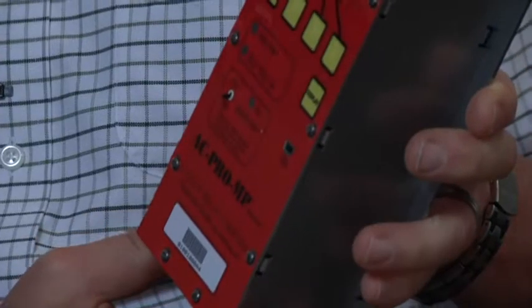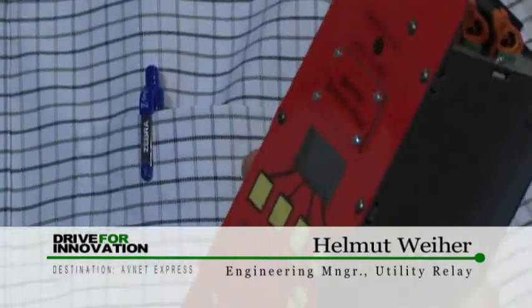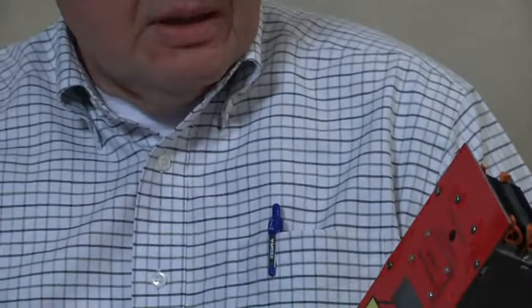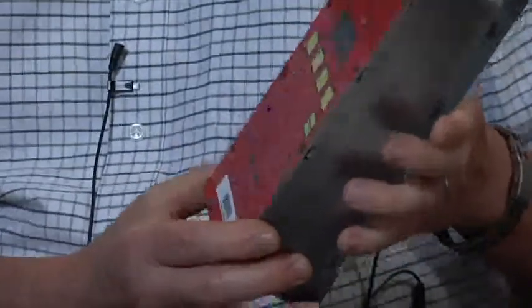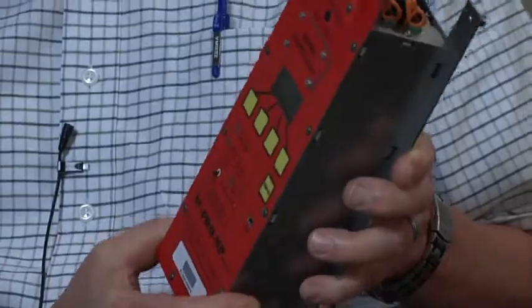So you have a new product out here in the last 6 months or so, the AC Pro. Tell us a little bit about that. Yeah. Well, this is actually the AC Pro MP, and it's specifically designed for the Merlin Gerin MasterPact MP power circuit breaker, which is an insulated case circuit breaker. It's an older breaker, but it's not being manufactured any longer. However, there's a lot of these breakers used in critical applications like data centers. And the existing trip units that were on that breaker, they're starting to fail. So there's a problem. It's very expensive to replace the breakers. So we designed a direct replacement trip unit that takes the place of the old trip unit.